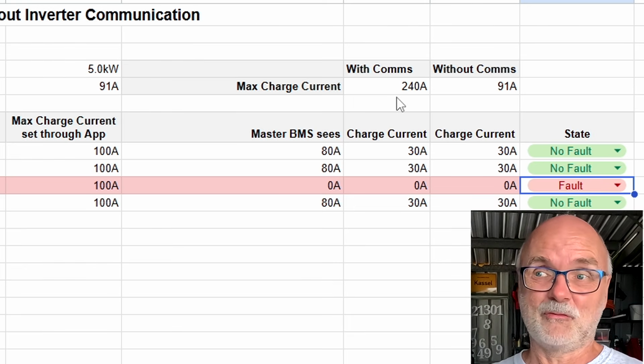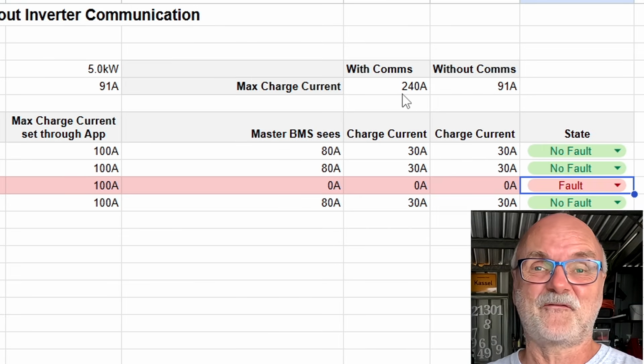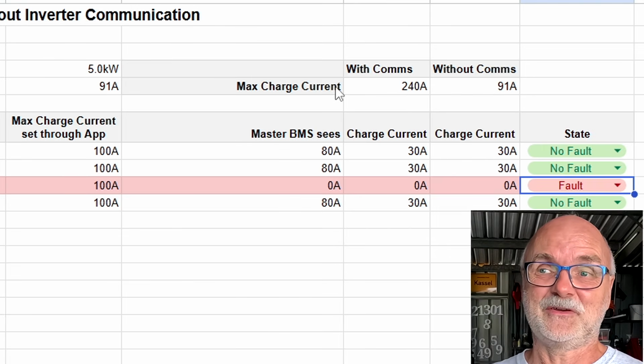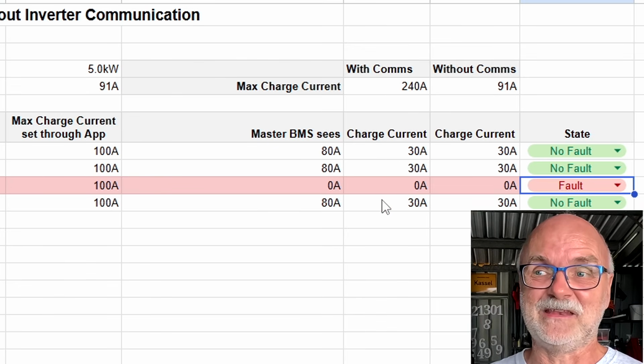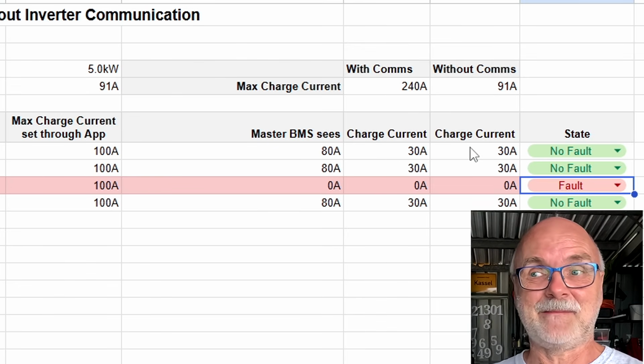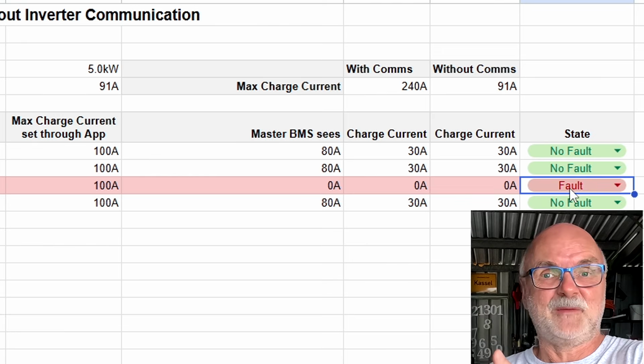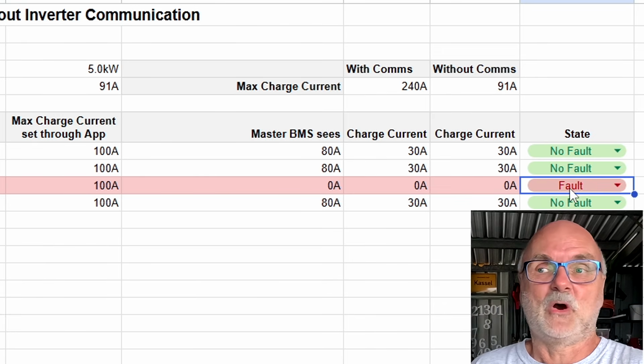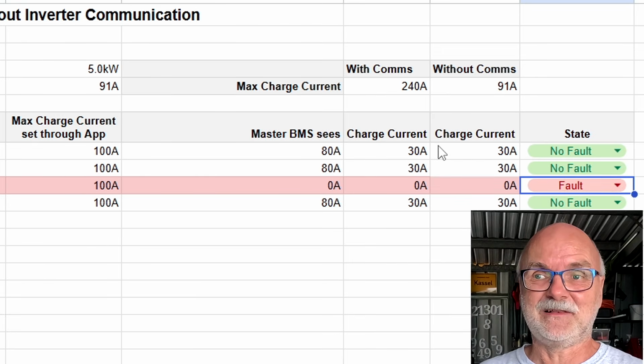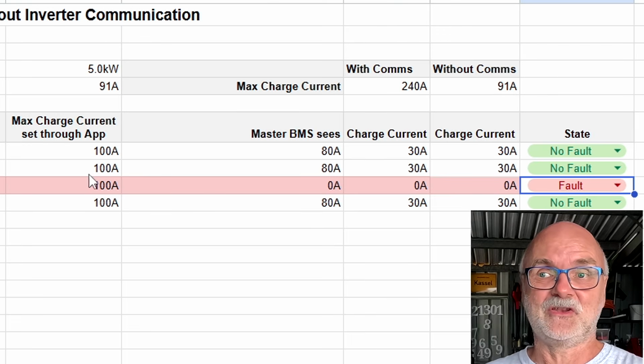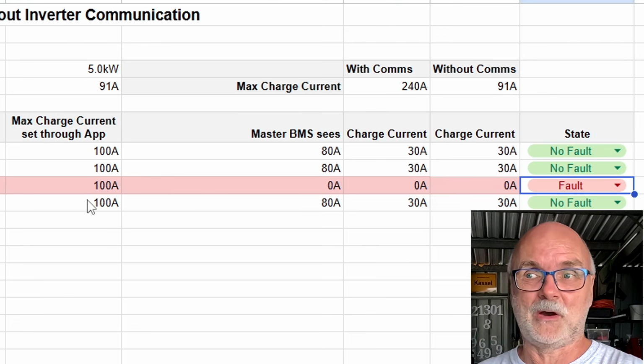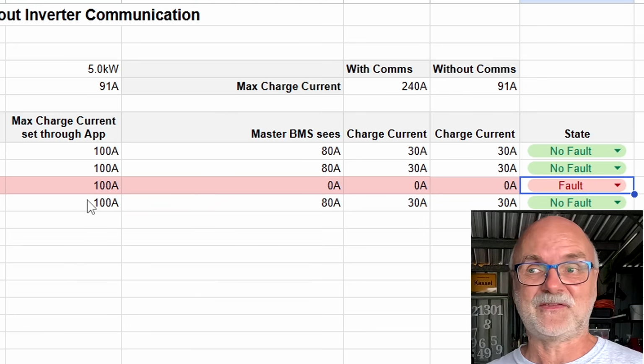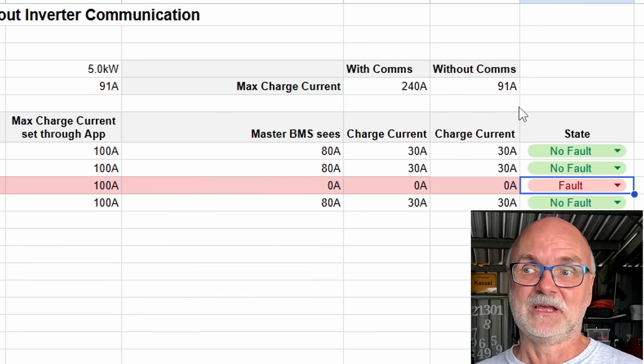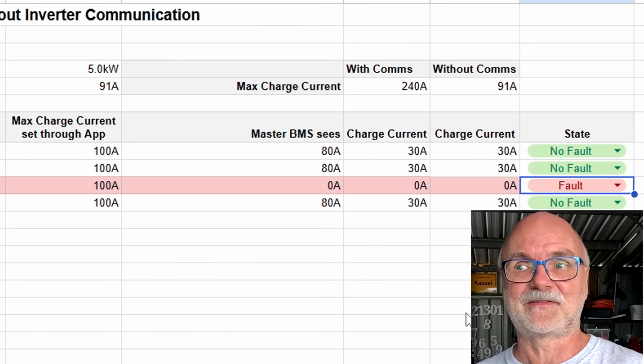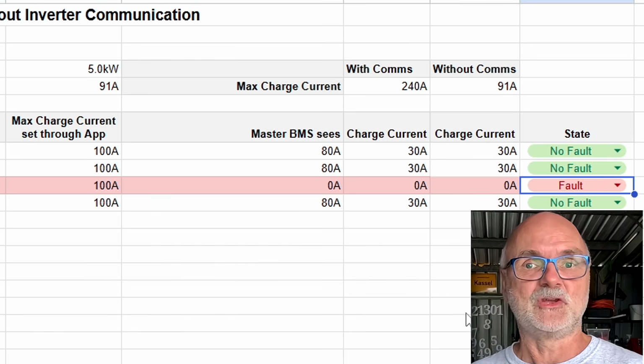The master would now report, okay, charge me with 240 amps only. Yeah, because your system still can do only 90 amps. It would be 30 amps into each battery. Exactly the same as without communication. If one of your BMSs has a fault, it would make no difference. Everything is safe. We are still far under these 100 amps here. No issues at all with or without communication. The only difference is you don't get a notification. So if this happens on a regular basis without communication, you would not know.